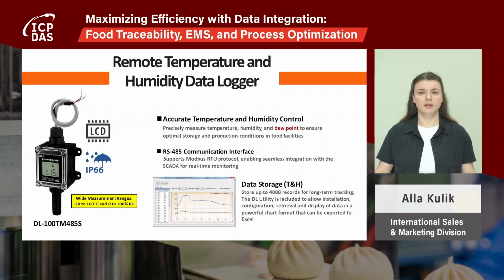The DL100TM485S remote temperature and humidity data logger monitors temperatures from -20 to +60 degrees Celsius and humidity from 0 to 100%. It contains an LCD display to show a variety of data such as temperature, humidity, dew point, and module ID. With storage for 4088 records, it provides easy access to historical data for compliance and analysis. Its RS-485 Modbus interface enables smooth integration with SCADA systems for real-time monitoring, and the IP66 front panel protects it from dust and moisture in the factory environment.